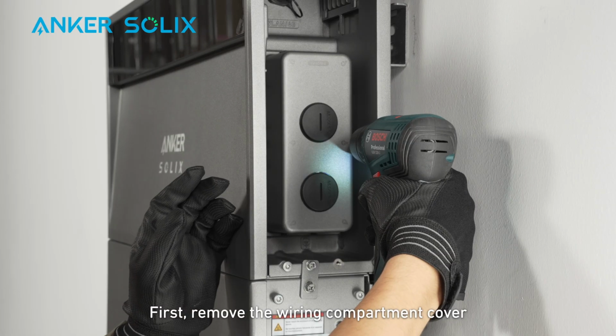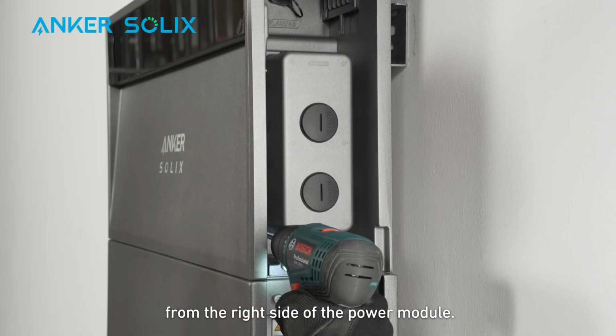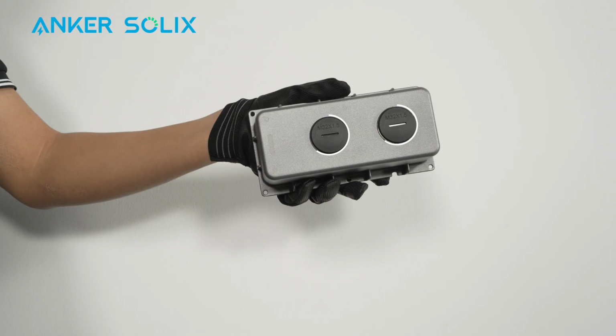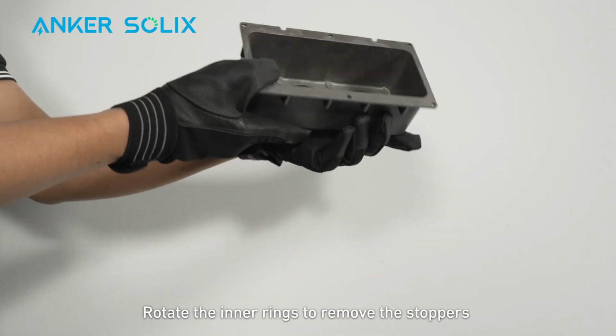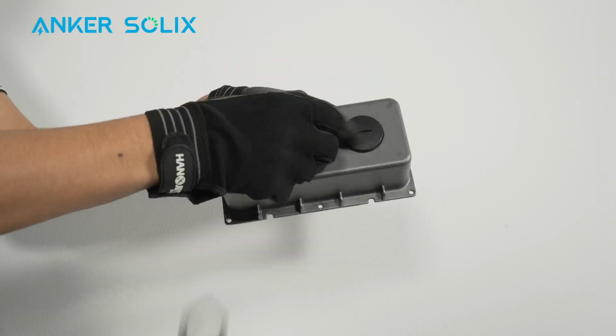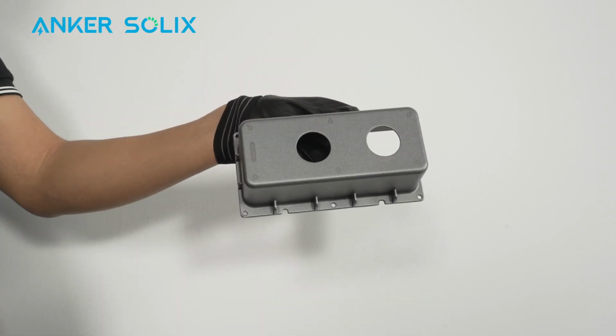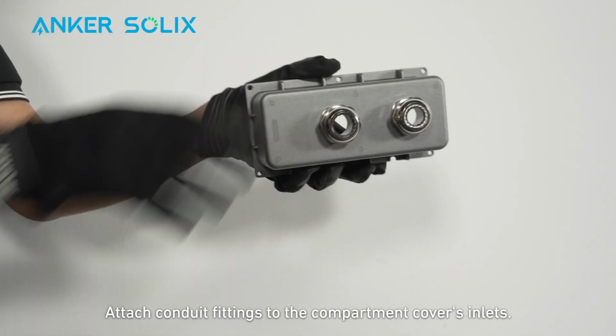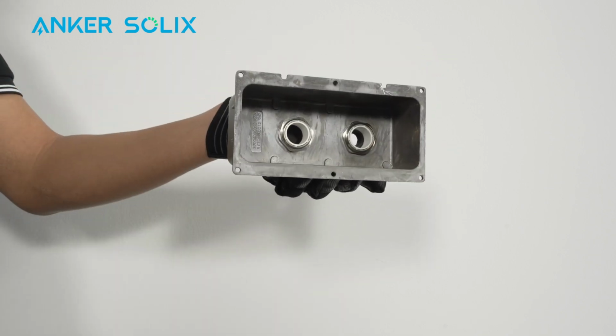First, remove the wiring compartment cover from the right side of the power module. Rotate the inner rings to remove the stoppers from the compartment cover. Attach conduit fittings to the compartment cover's inlets.